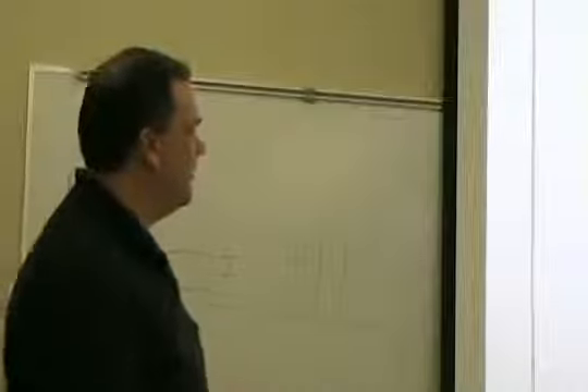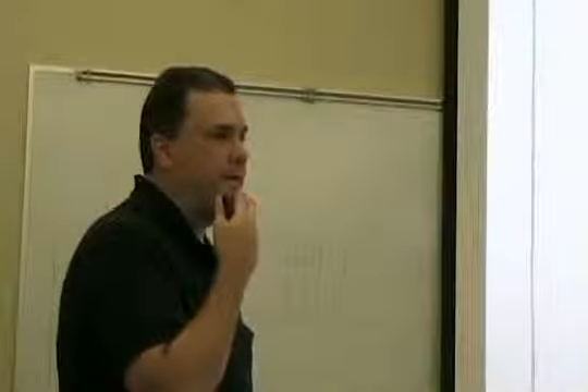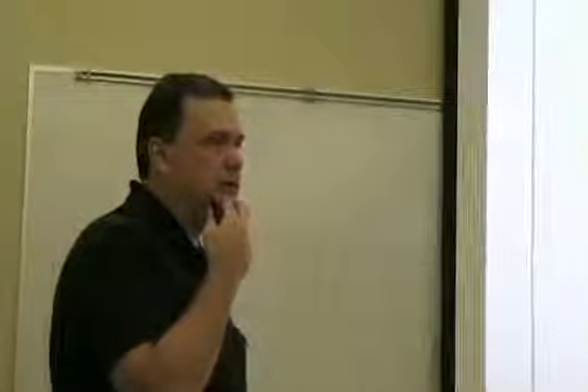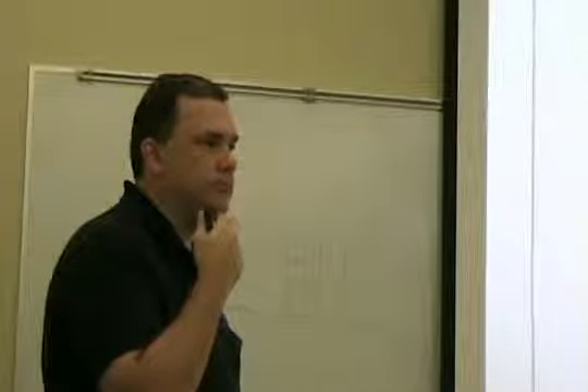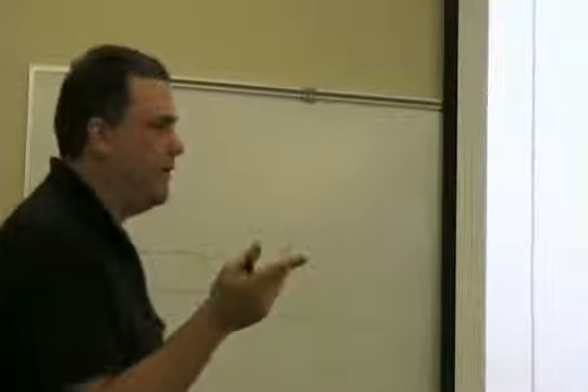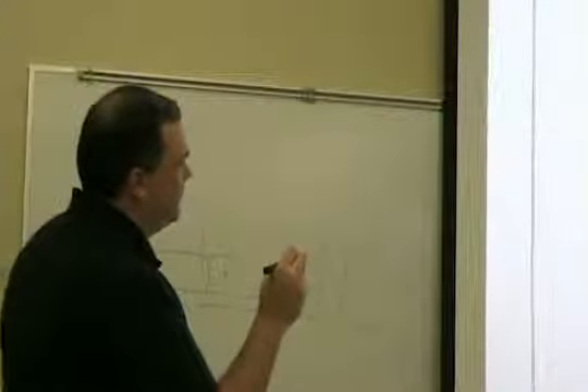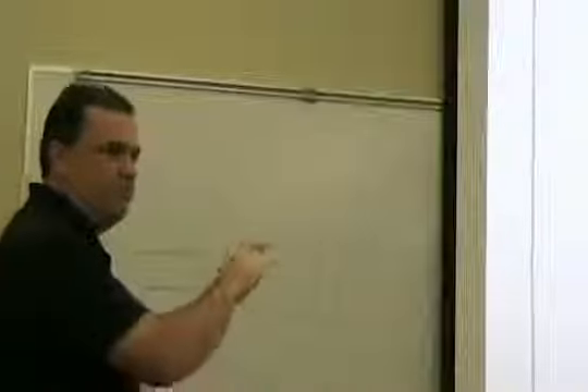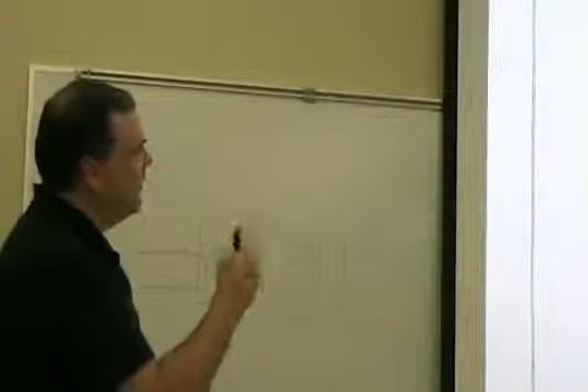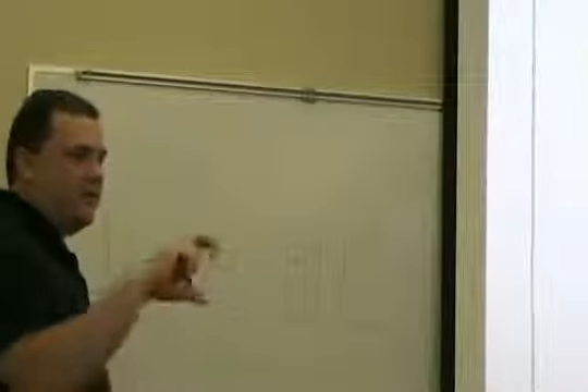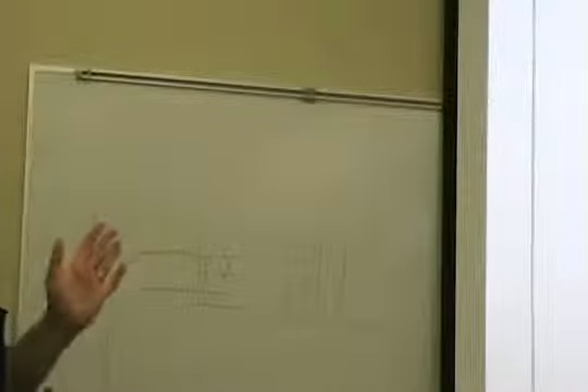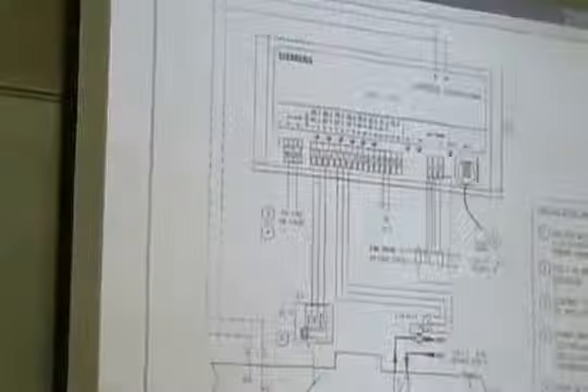Can you explain how the hot water valve and the damper modulates whenever it's a DO? Okay, you've got 2 DOs for each one. DO1 and DO2 both control one motor. DO3, DO4 both control the other motor. These motors, they used to call them stepper motors. I don't know if that's a proper term anymore or not, but you put power on them one direction. You got 3 terminals that come out. You put power 24 volts on one set of wires. That motor's going to drive one direction.